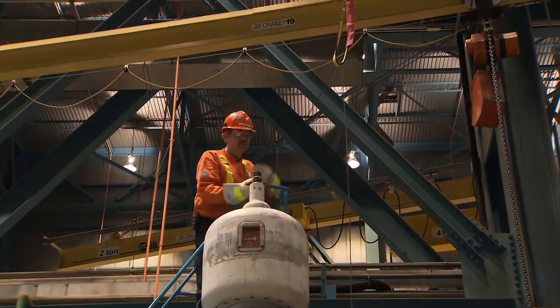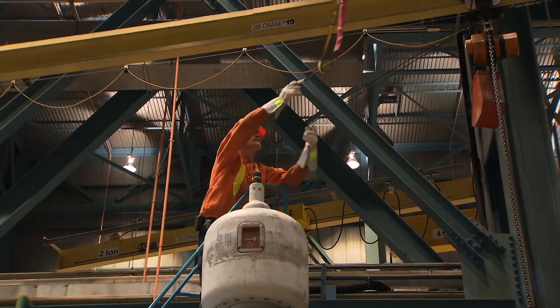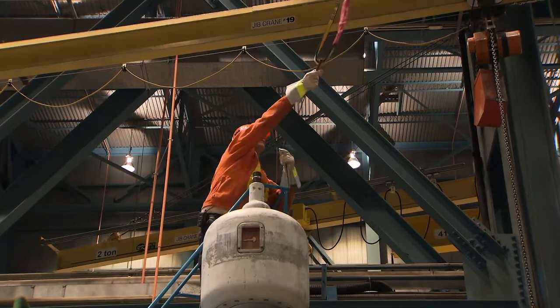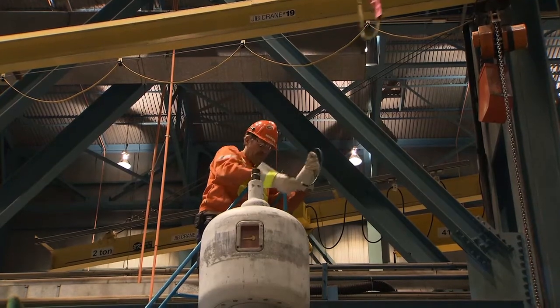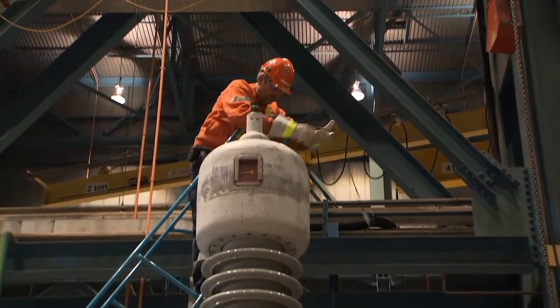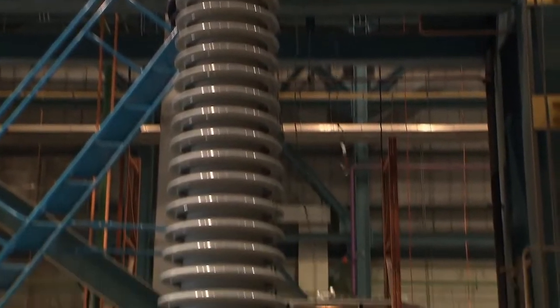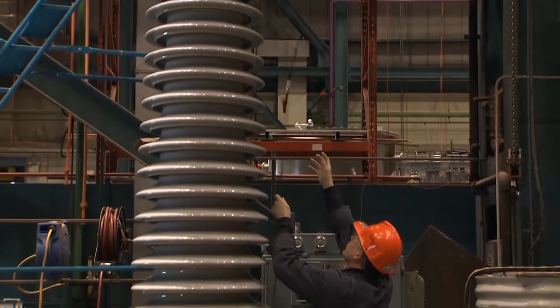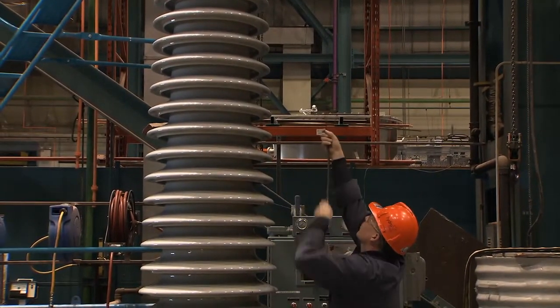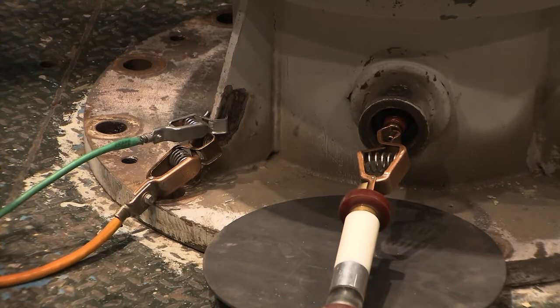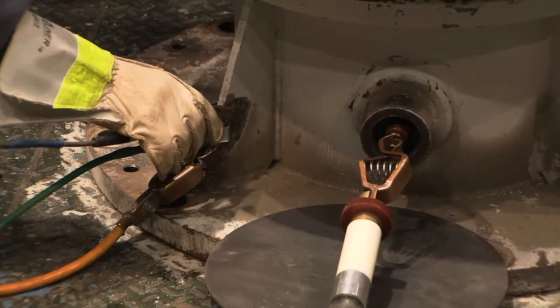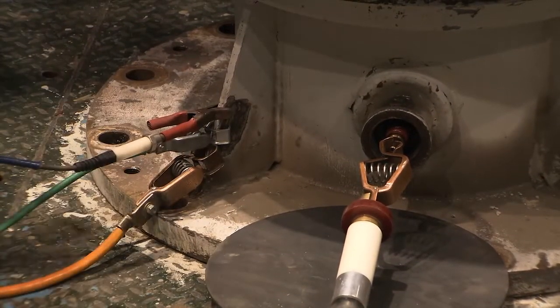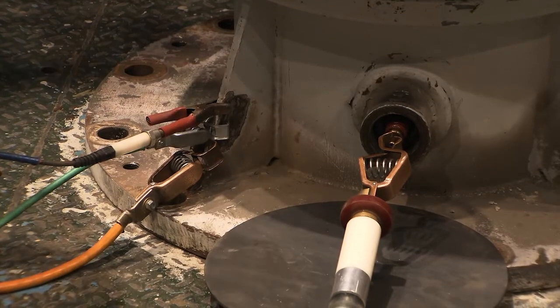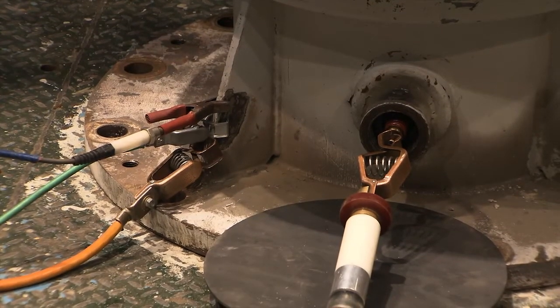Disconnect the low voltage lead from the top of the conductor core and connect it to the flange in preparation to conduct the C2 test. The high voltage lead will stay connected to the capacitance cap.